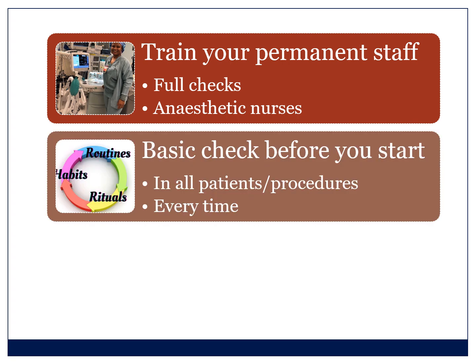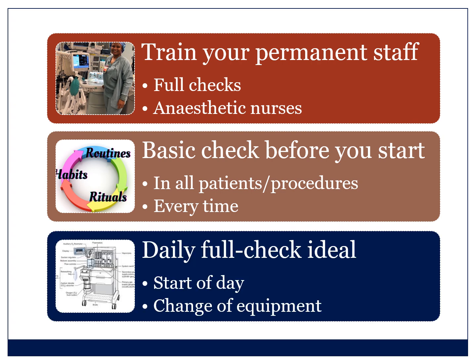There's then the full check that you want someone to do every day, but there's a basic check before you start in all patients, all procedures, and you do it every time. I'm going to go through that today because I think that's an important part of this. And then the daily full check, which, as I was mentioning, you can use your anesthetic nurse to assist with. Start of the day, or when you change equipment, like you put on a pediatric circuit or you change the soda lime or something like that, then you need to do a full check.